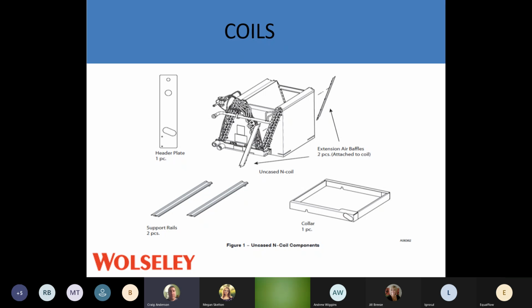So there are two ways to install it. You can flip it upside down to what it looks like right now and set the coil on top of it. Or you can keep it up the way it is, the way you took it out of the box, and mount that template in the plenum. As long as you're making sure that whole opening of that template is wide open, then you're 100%. So when you set that coil back in, before you put a patch on it, that coil is going to be 100% open. If you put rails in and slide that over top, chances are you're going to block off that right-hand side. I've been to a lot of job sites, traveled a lot of miles just to confirm that the coil has been blocked off on the right side.